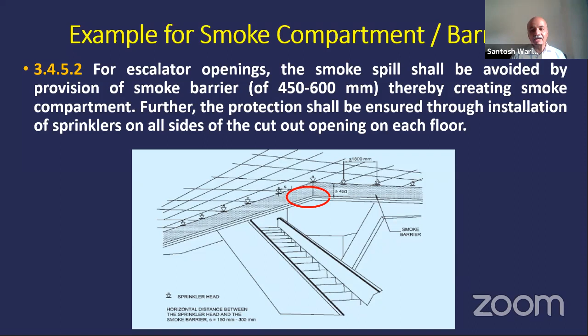and you can have secondary fires. To restrict this, provision is made where you can have smoke barriers along with the escalators or the open passages or the atriums, and a sprinkler system provided along with it, so that in case of fire the hot smoke will come up to the sprinklers and the sprinklers will get activated immediately, and the smoke can be cooled down and the fire cannot spread to the upper floors. So that is the intent of this smoke compartmentation. Before going to the other details, we have to first understand the basic concept of any building.